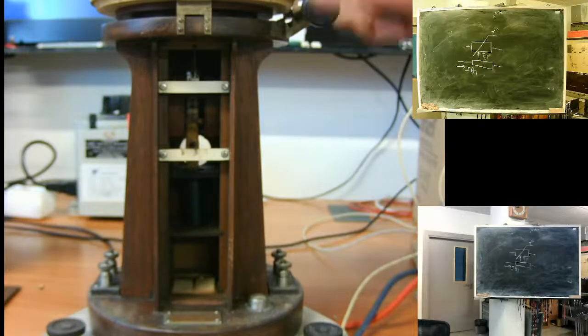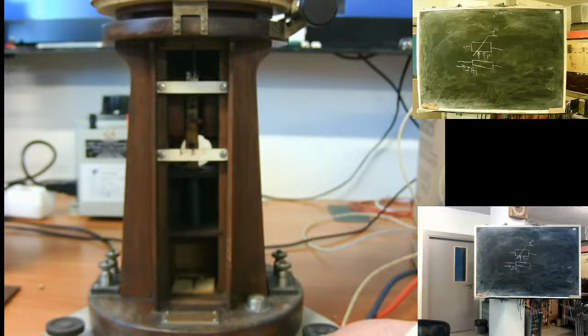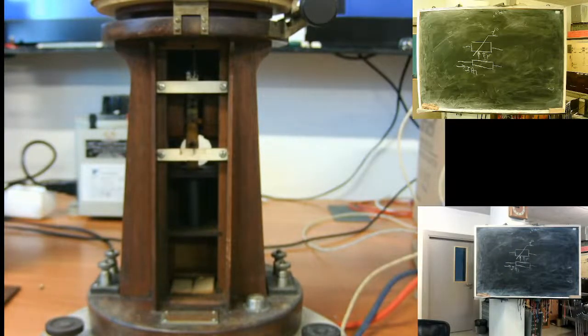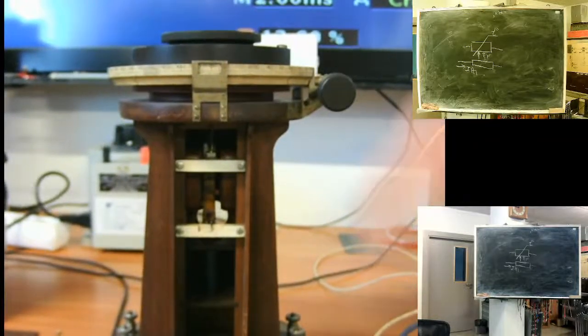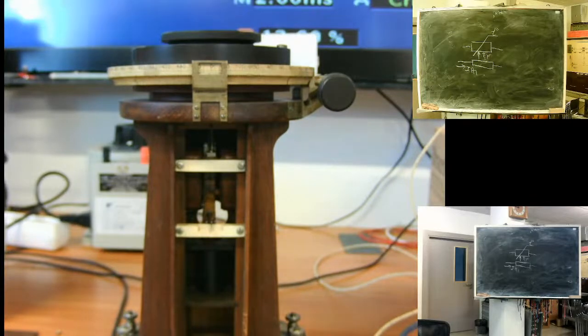Here, reading is done in a different way. We need to turn this upper limb. It has a spring connector, and we need to set this index at the zero point here, and later read some related values from the upper scale, and somewhere there should be a chart. Which number on the upper limb corresponds to which power? Real reading of watts is from the chart, converting these related values. It's from 0 to 500 to the real watts.